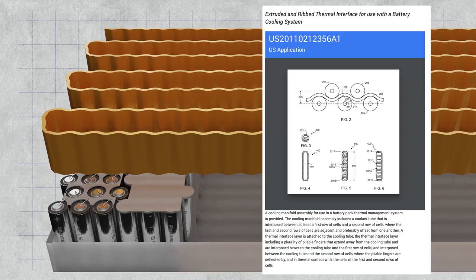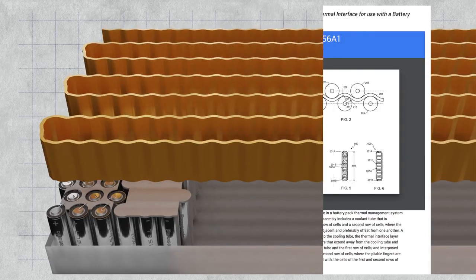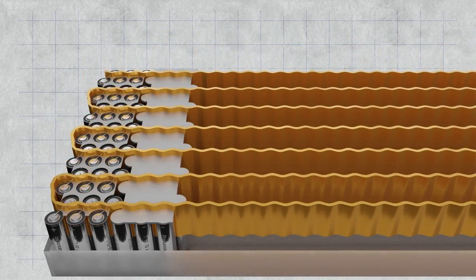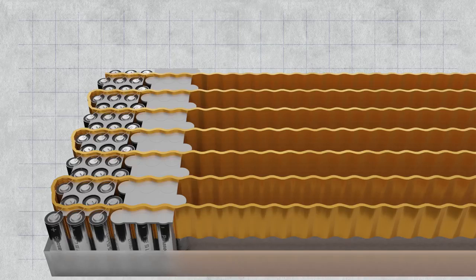The cells are covered in a thermal interface material, which is a poor electrical conductor but a good thermal conductor. That allows good contact between the aluminum battery casing and manifold. A water and glycol coolant mixture is pumped through this manifold, where heat from the batteries can be transferred, just like liquid cooling for your PC or a conventional liquid-cooled gas engine.